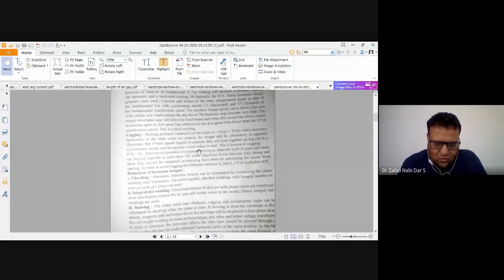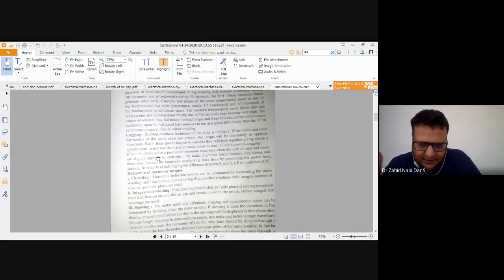So if the stator and rotor harmonics of the same order are present, the torque will be alternately in opposite directions. But if their speeds happen to coincide, in easier words, they will lock together, giving rise to a synchronous torque, and the machine would refuse to start. The mathematics behind it, as I told you, is Ns minus Nr divided by Ns. So this phenomenon is called cogging.